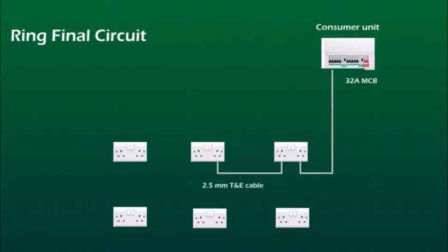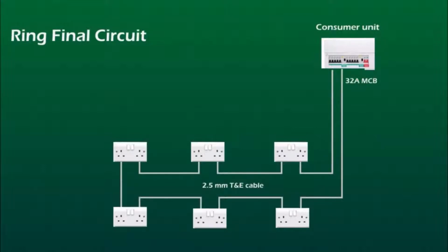Another commonly used circuit for socket outlets is a ring final circuit, or simply ring. So again, top right corner we've got the consumer unit with 32 amp MCB, and let's say we've got 6 socket outlets on this ring. 2.5 twin and earth cable from consumer unit goes to the first socket, then from socket to socket, and from last socket the cable goes back to the consumer unit. The 2 brown live wires from both cables we connect to the same 32 amp MCB.